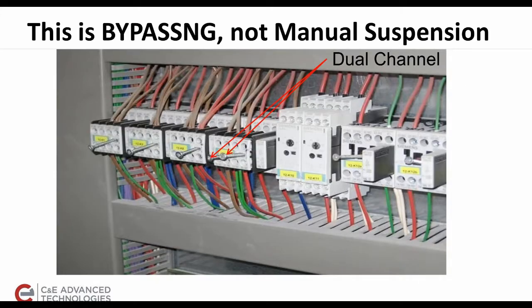This is not manual suspension, this is bypassing. Notice here that the individual that did this had some safety training, because this is indeed a dual channel bypassing.